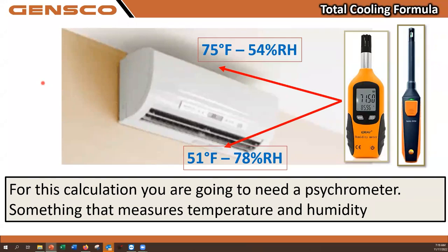Even though we're going to be removing moisture from this unit, we are condensing the air and making it more compact. And thus the water that remains in the air after it passes through the unit is going to produce a higher relative humidity, even though it is actually less grains of moisture. This confuses people sometimes, but that's the actual fact of what can happen.